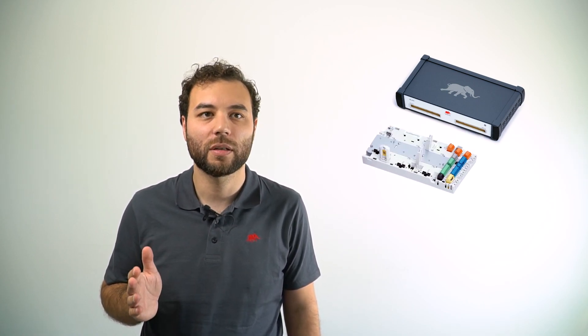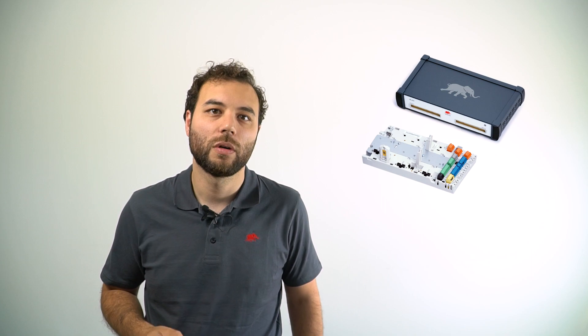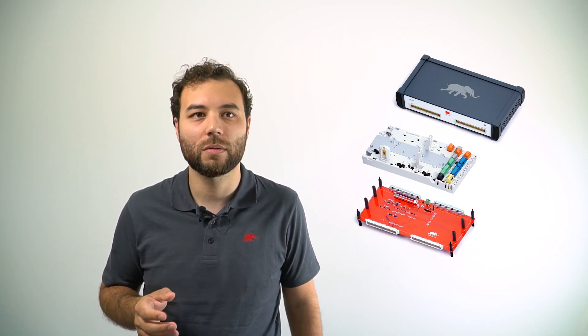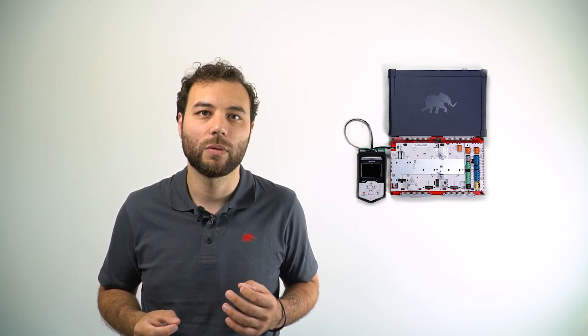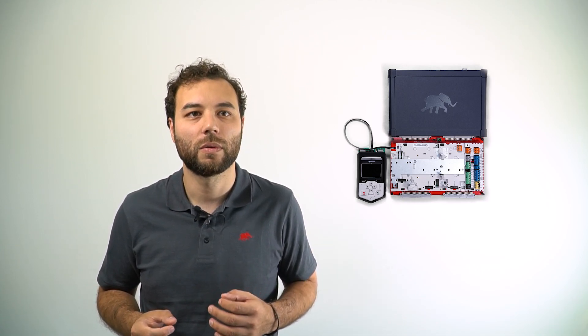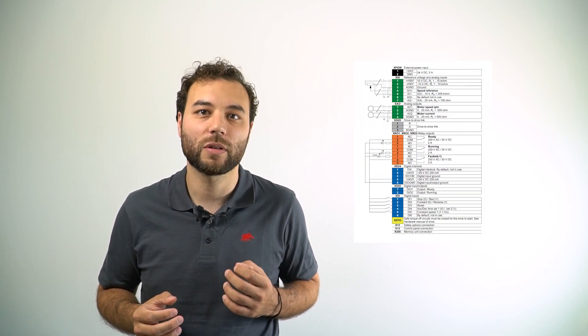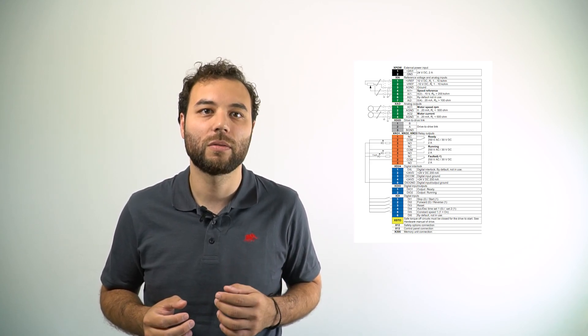Let's take a look first at the setup we'll be using and then at the motor drive model that we'll be simulating. Our test bench will use our 200 nanosecond time step Typhoon HIL 404 real-time simulator, an ABB ACS 880 industrial motor drive ECU, and an interface board specially designed to scale the required analog and digital interface between the HIL device and the motor drive controller. The ECU is configured for external control with factory macro enabled. Start-stop, direction, and reset commands are accessed through the controller's standard IO interface directly connected to the HIL outputs.